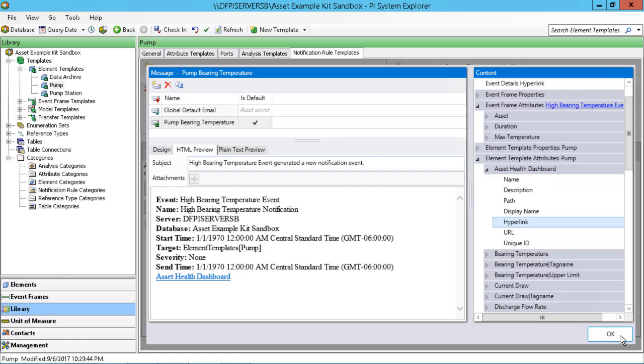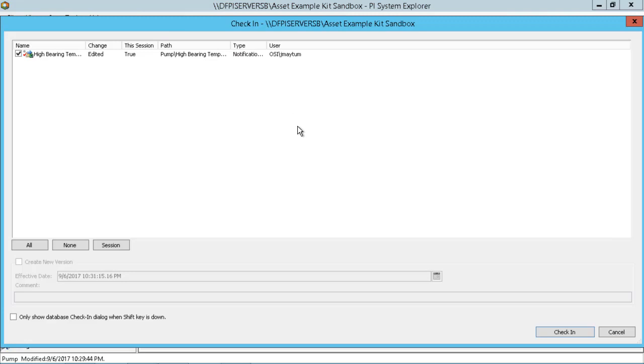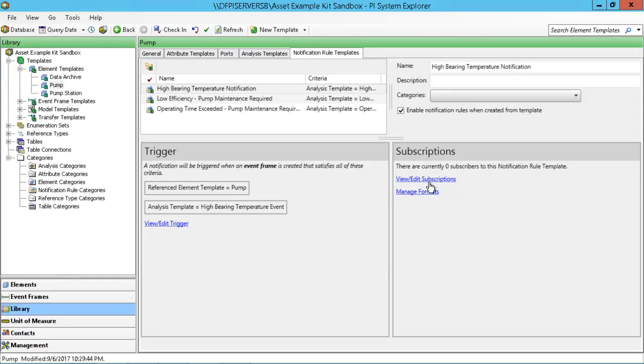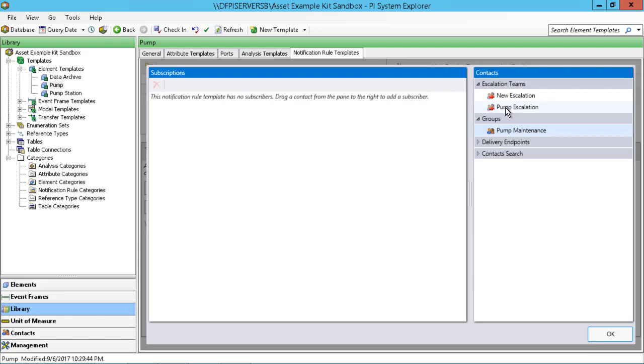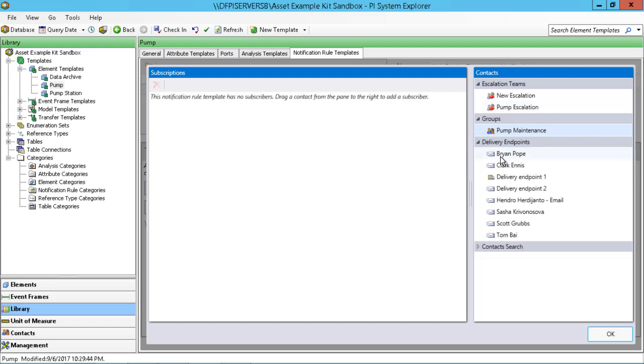We'll click OK to save out the pump bearing temperature format, check that in to commit those changes, and then edit our subscriptions. We can see there's nothing there yet. We can click on pump groups — there's a pump maintenance group here. We could also include escalation teams: send it to team A, and if no one acknowledges, send it to team B, and so on. One other thing to point out is that we have multiple different types of delivery endpoints.